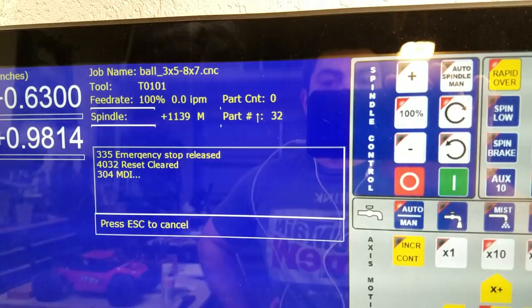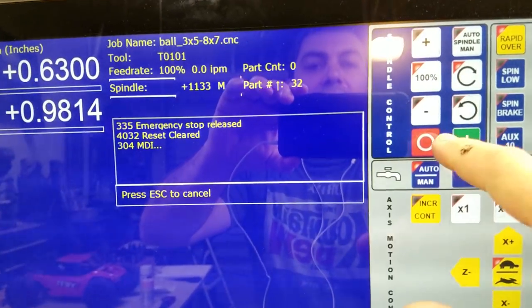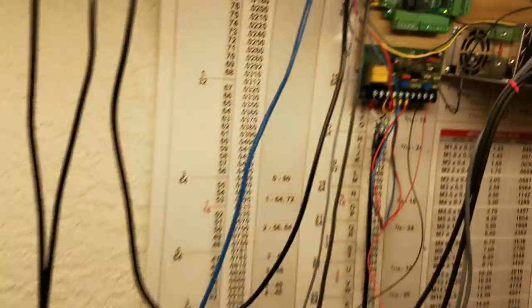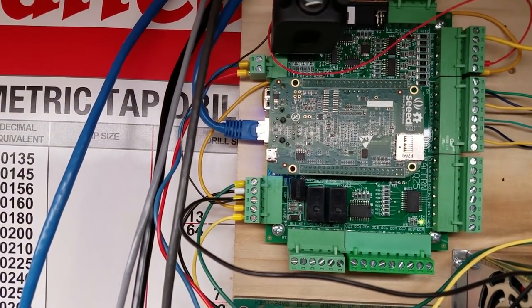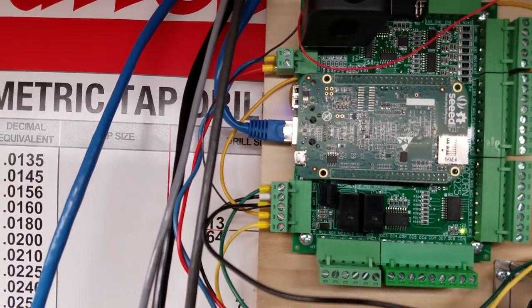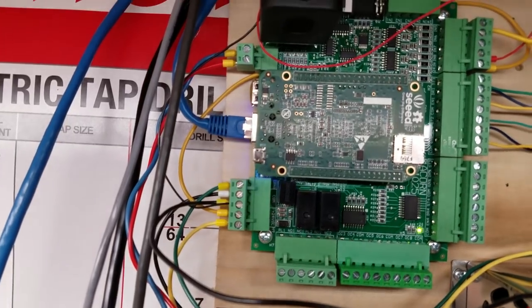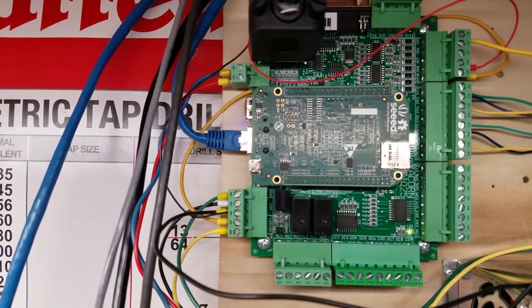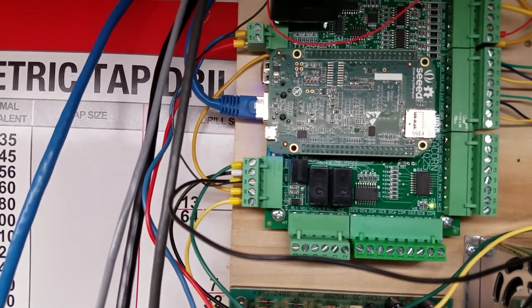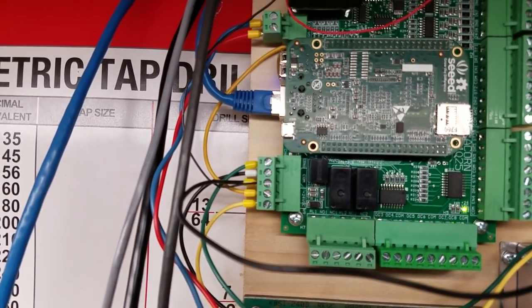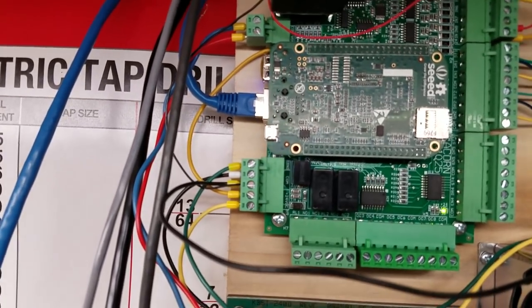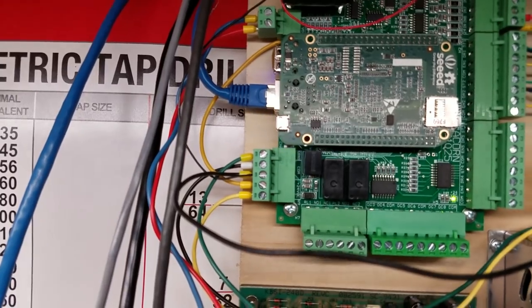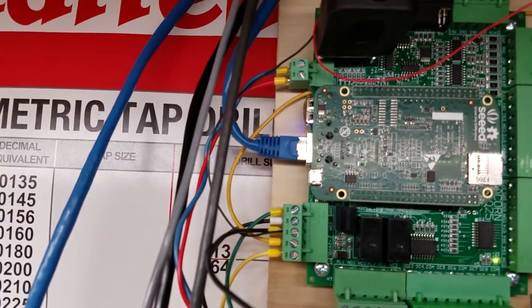What I did, so here's kind of a little secret you need to know. The output that comes out of the Acorn, right now, the way this is designed, the way it works, it's designed to send a zero to 10 volt signal to a VFD, a variable frequency drive. Variable frequency drives are very precision electronics, very accurate. Even the cheap ones that you buy, they're very linear in their input. So if 10 volts is 100%, full max RPM, five volts will be 50%. One volt will be 10%. They're very linear in the way they read the input voltage. They're very precise.